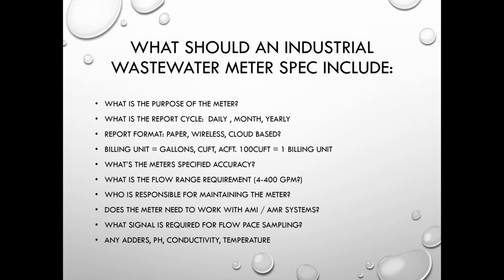If you're looking at a facility with 2 faucets and the average faucet runs at 2 gallons per minute, that's 4 gallons per minute. If they've got an 8-inch mag meter that starts reading at 33 gallons a minute, you're obviously missing all of that flow. So depending on the range and what you specify as the range, you could be missing quite a bit of flow on that low end.